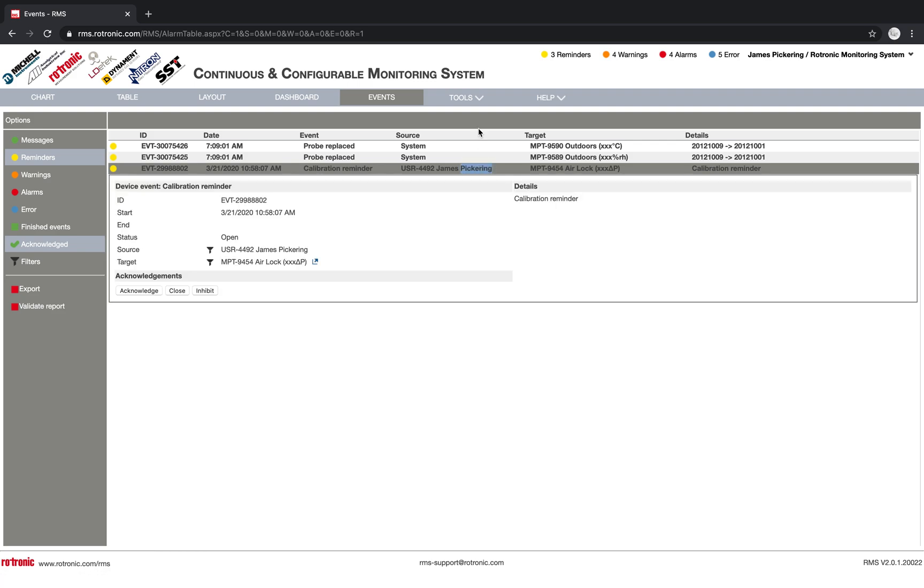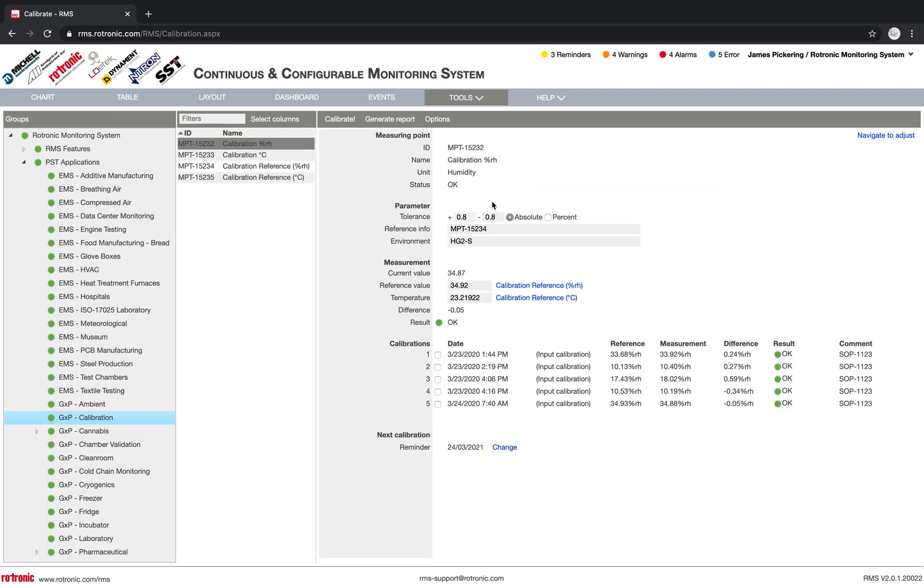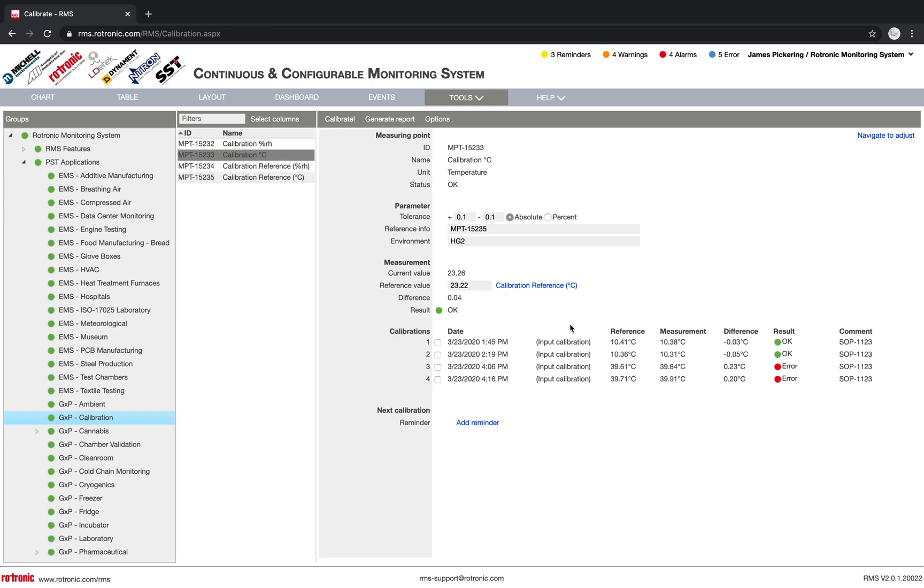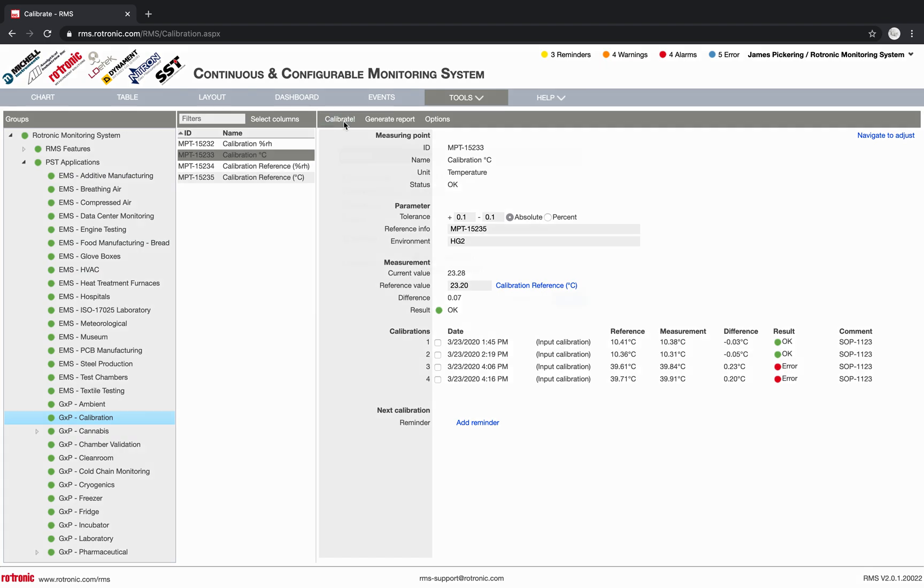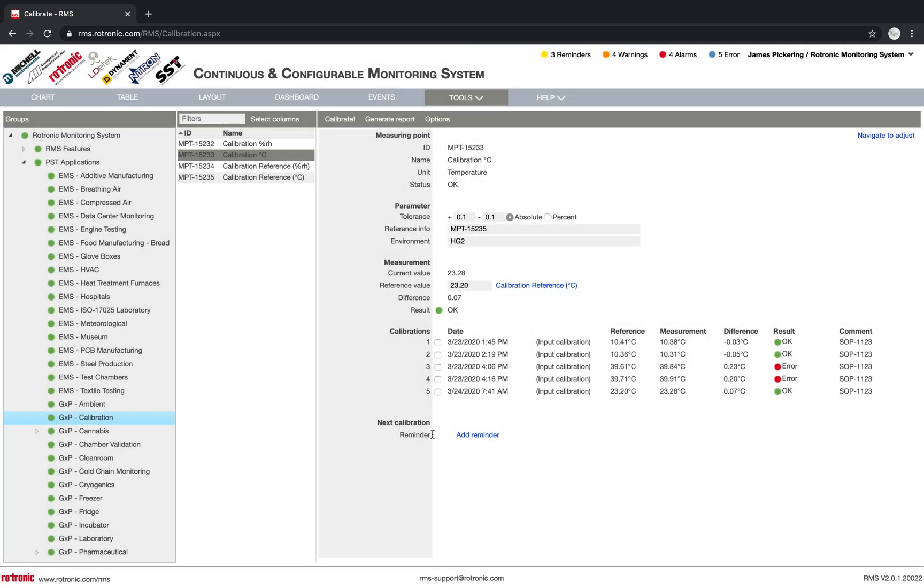So if we head back now to our calibration, we can also see what happens when there is an error. So if I go into the temperature side, yesterday, I added a few errors by creating a very, very low tolerance. So here we can see exactly the same overview. We see here that we've taken a reference to the temperature. We can see a difference of 0.07 compared to the current value. And same thing here, I can click on calibrate. Same thing, we've been using an SOP, so I'll put an SOP in, and we click on okay.